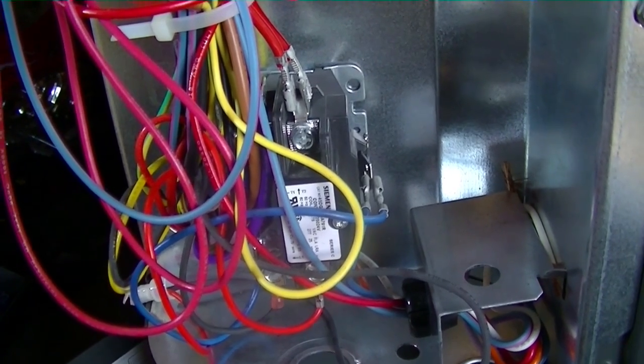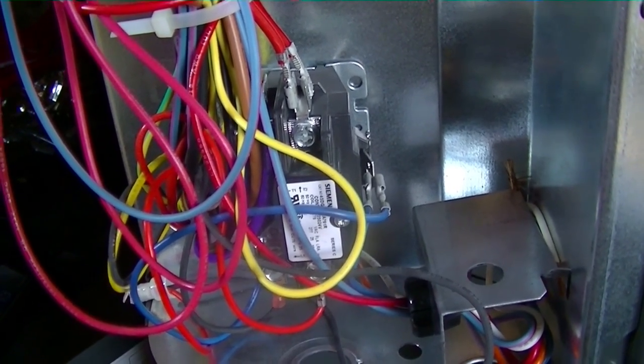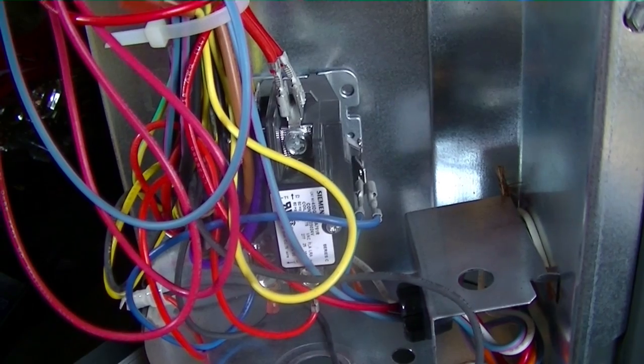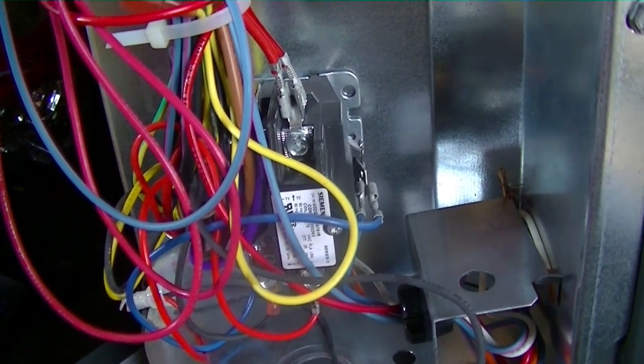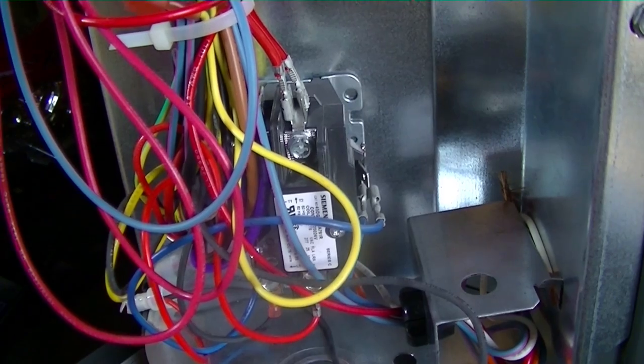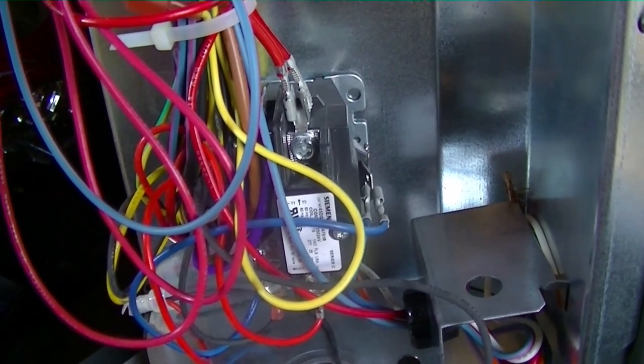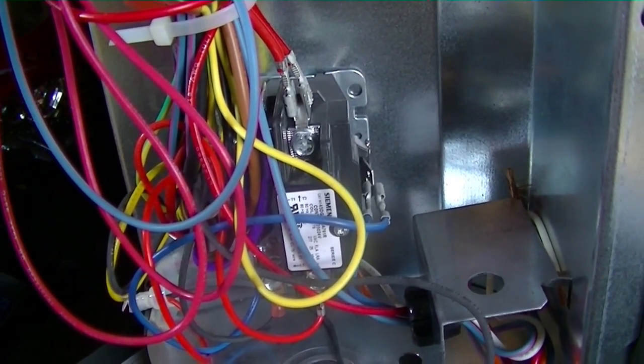In regards to an outdoor fan motor, each one of those wires has a specific winding. Common is black for this particular motor, brown is start, purple is run.